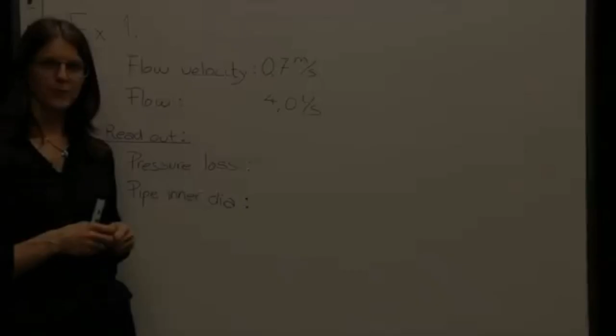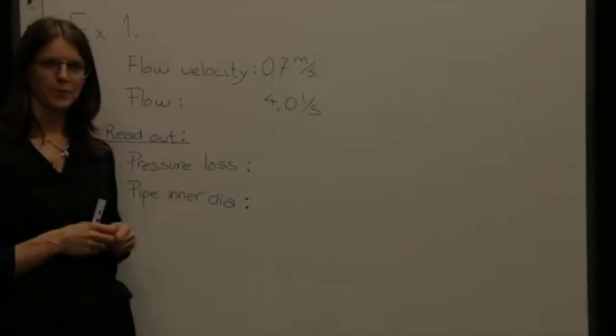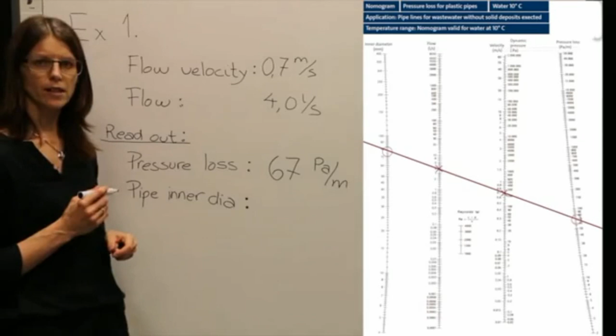Let's take an example. Let's take example number 1. Here we have a flow velocity of 0.7 meter per second and a flow of 4 liters per second. You mark that on the two scales on the nomogram. You put a straight line through these two points, and with the intersection you can see that the pressure loss is 67 Pascal per meter. And the straight line intersects with the pipe inner diameter scale at 79 millimeters.